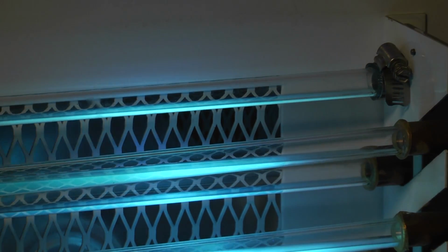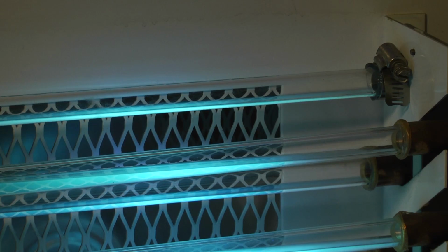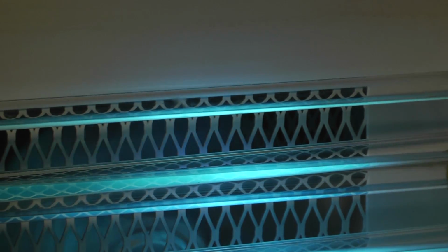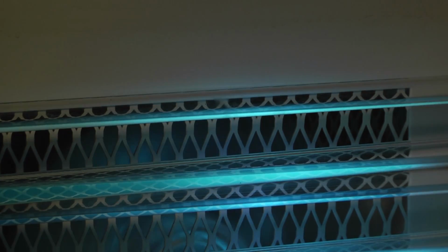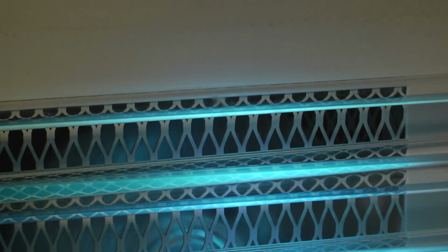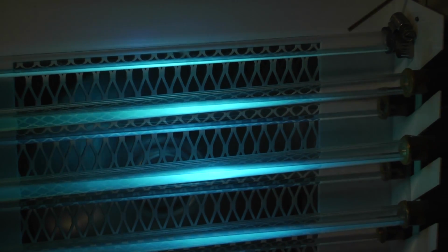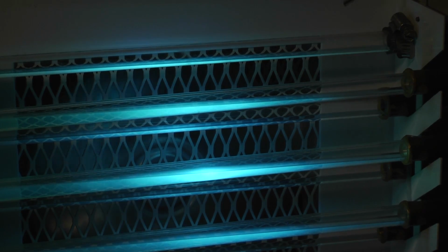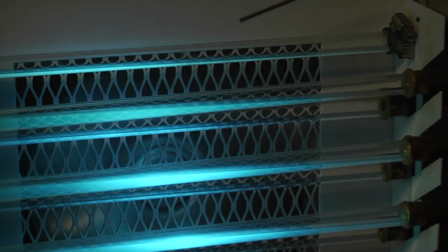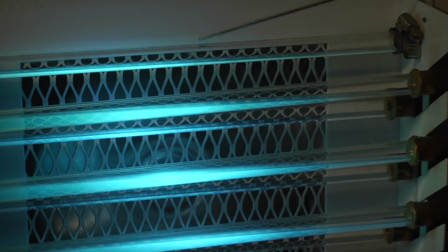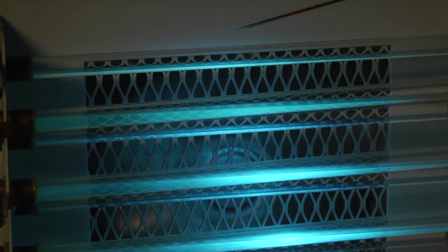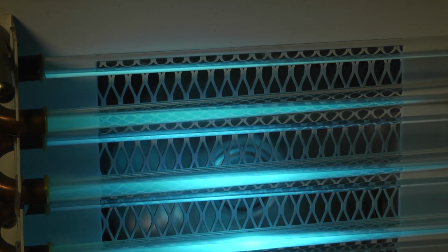It's 100% gas. The first thing the condenser does is, now that the compressor has raised the temperature of the refrigerant above the temperature of the room air that's passing over it, it starts to throw the heat away from the refrigerant to the air passing over it. And what we can see in this first row is that some refrigerant vapor is starting to form. And as that refrigerant vapor is starting to form, we are at the saturation point, or we're dropping to the saturation point, doing the first thing that takes place in a condenser coil, the de-superheating of the refrigerant, or bringing it back down to its boiling or condensing point.